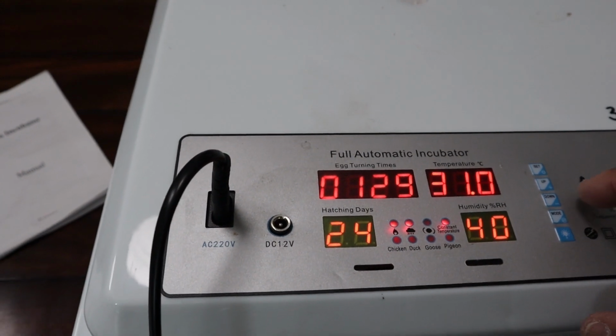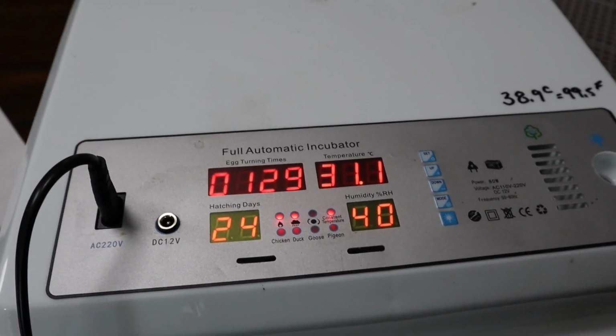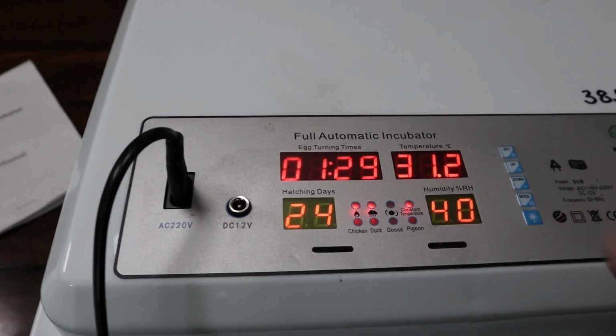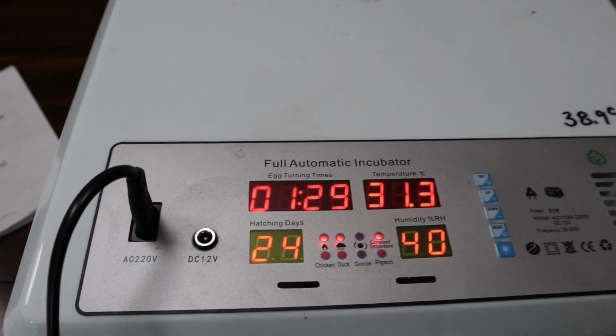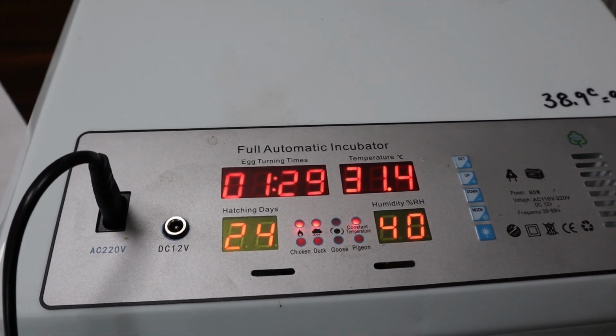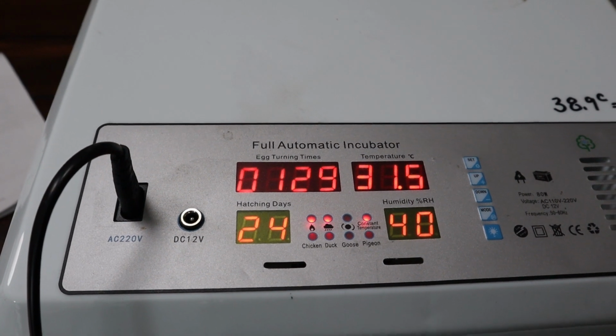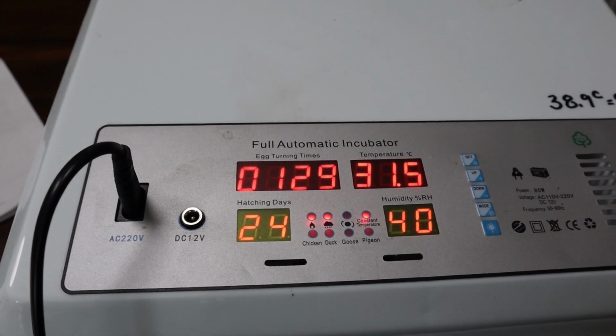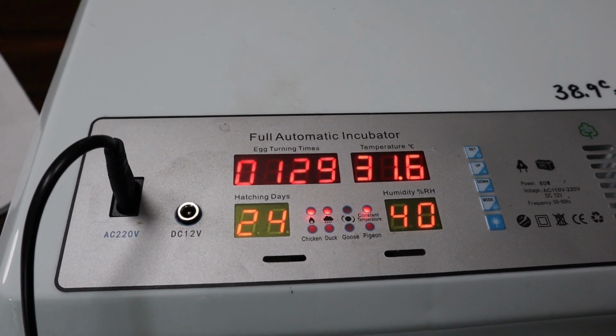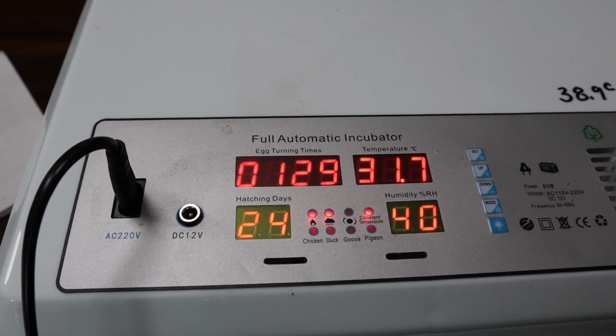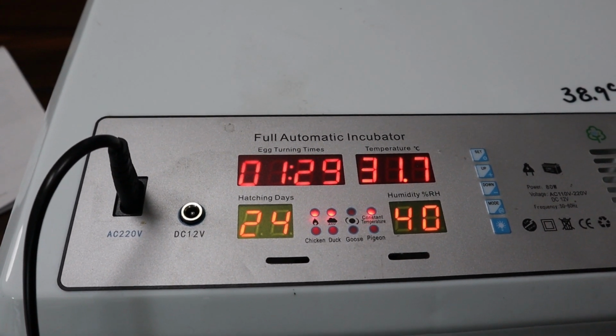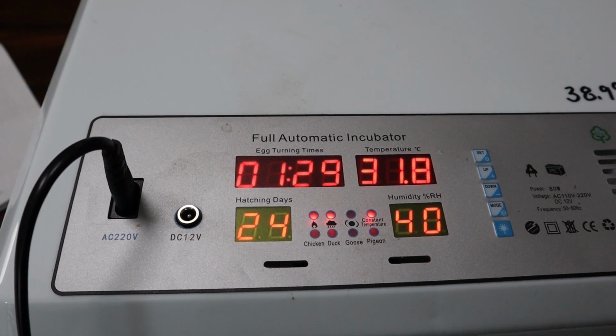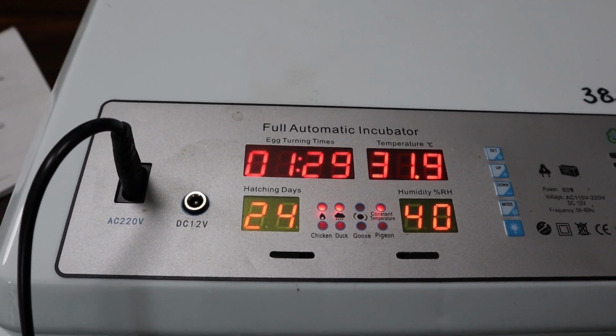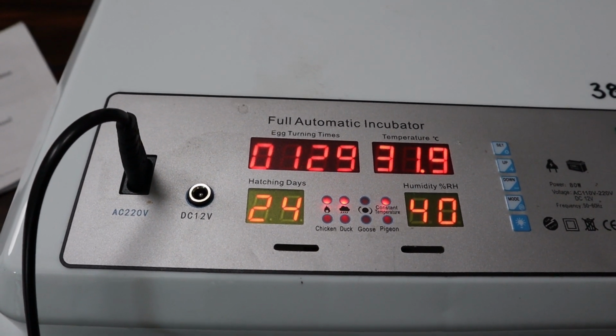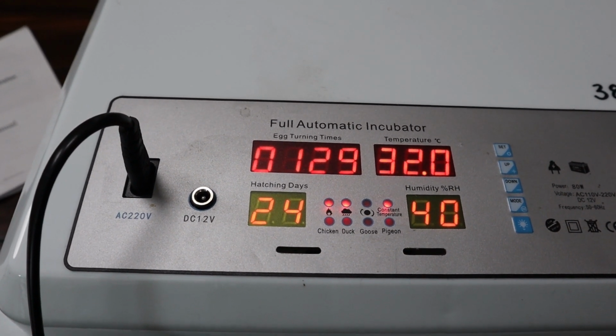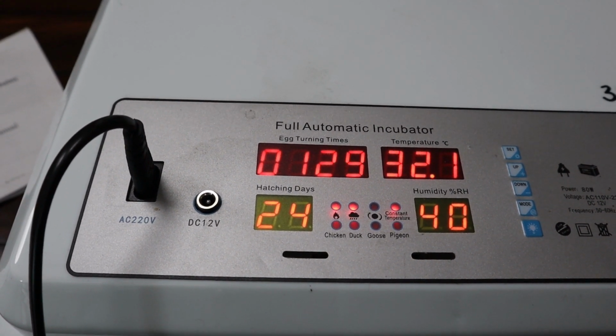The humidity level in this unit is at 40%, because that sensor is determining that. Now that's another thing that I found between the two humidity sensors. This is off by about 5%, in terms of the humidity level. So I had an external humidity unit attached to this, which also has an external hygrometer, so that I can read the actual humidity level on a secondary measure as well.